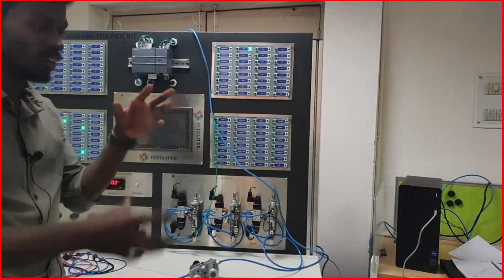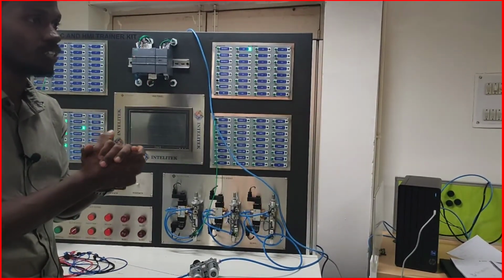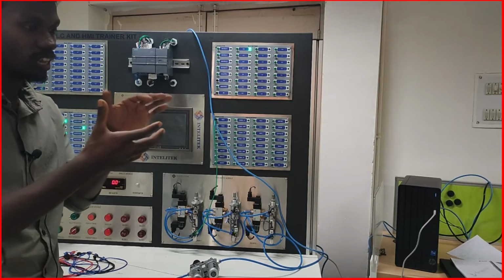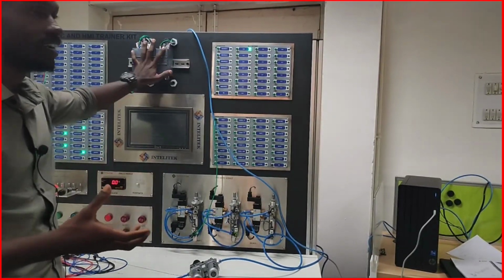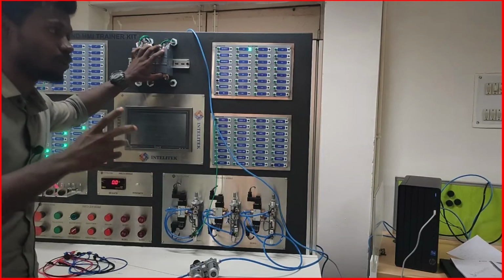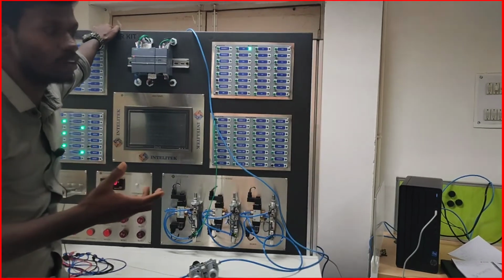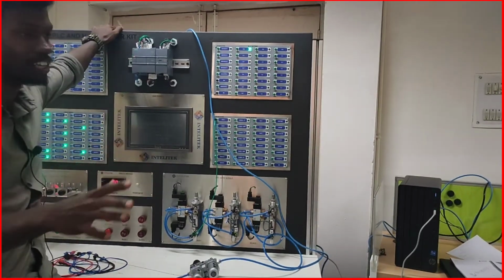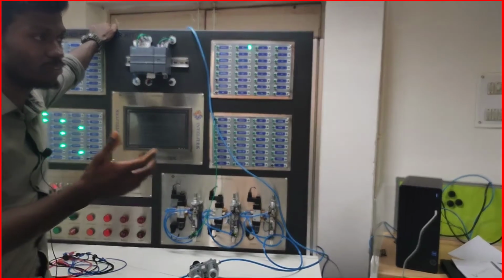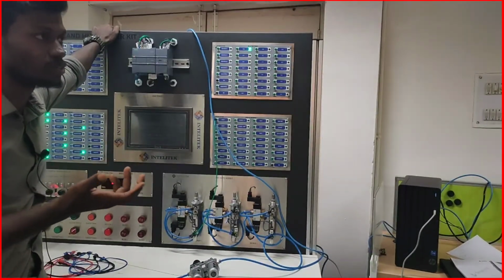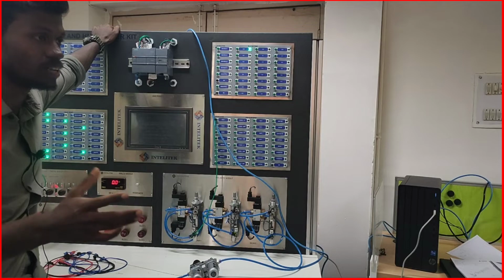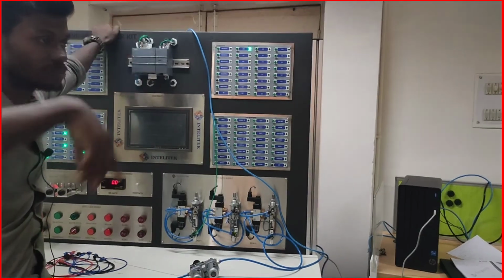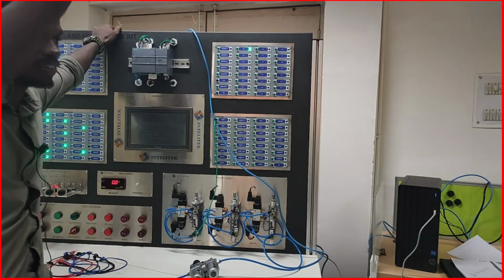That data is transferred via Modbus. So that Modbus data is transferred to BACnet IP, that is a protocol which they use. BACnet IP protocol is what Siemens uses for building management systems. That IP from BACnet IP uses BACnet MS/TP (Master-Slave/Token-Passing). Via that, the data is passed and transmitted to the management level.